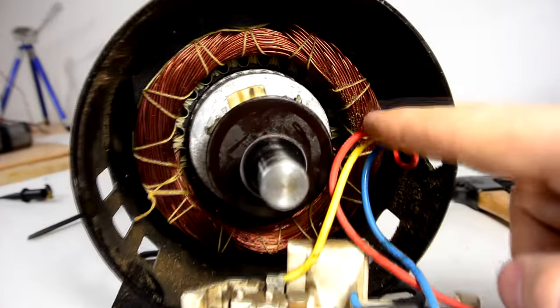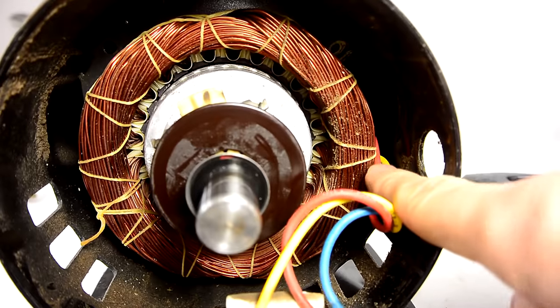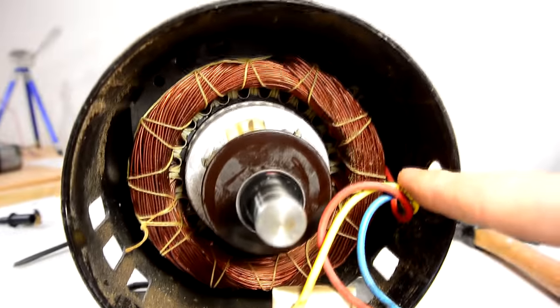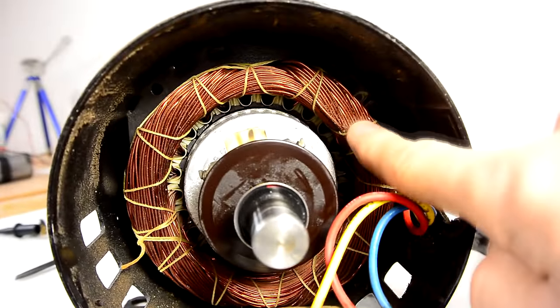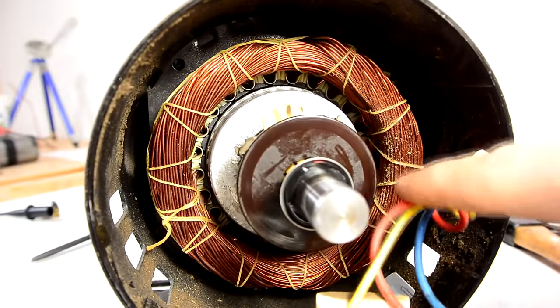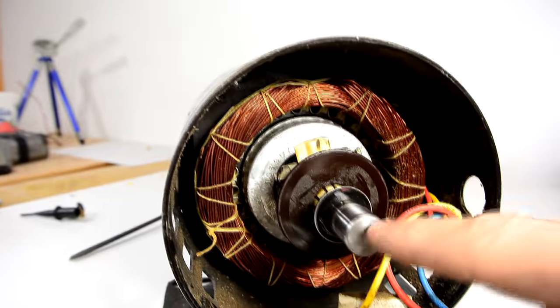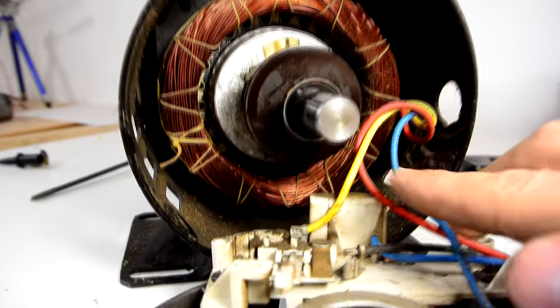Of course where there's a will there's a way so I could potentially dig out this connection in there and break it and bring out another wire. But the problem is there's no way to remove the stator from the case so I'd literally have to cut a hole in the case to get at it and I think that would just be more trouble than it's worth. So for all practical purposes this motor can't be reversed because they saved one wire.